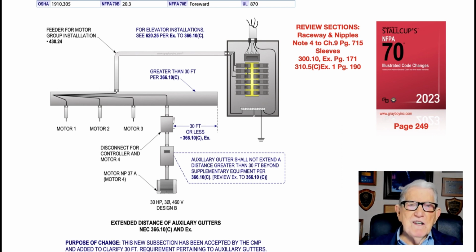But if you extend over 30 foot, then it becomes a wireway, and your rules for a wireway then kick in, in Article 376, and you do not go by the rules in Article 366 for auxiliary gutters. Now, we have to know the difference. That's kind of the way the industry looked at a wireway and an auxiliary gutter, when one would be classified auxiliary gutter and the other would not.